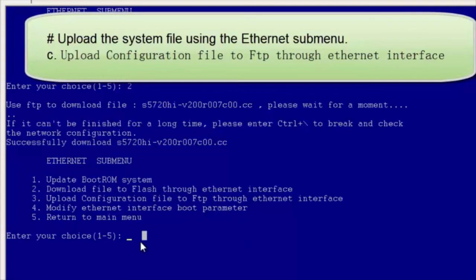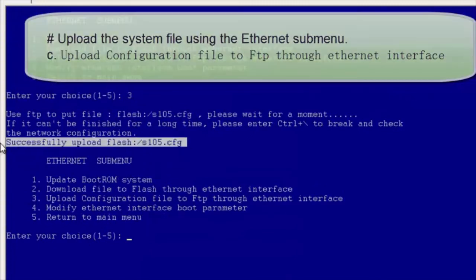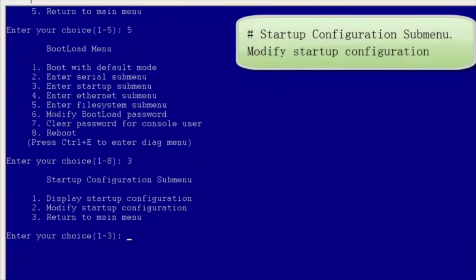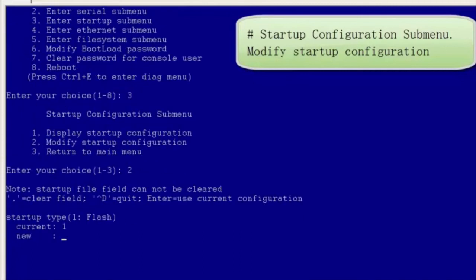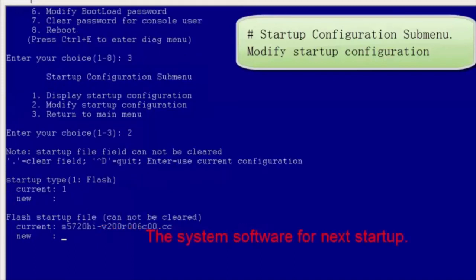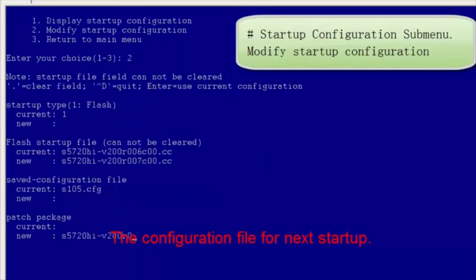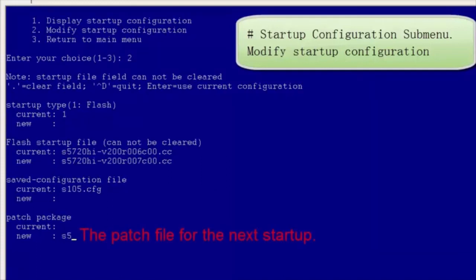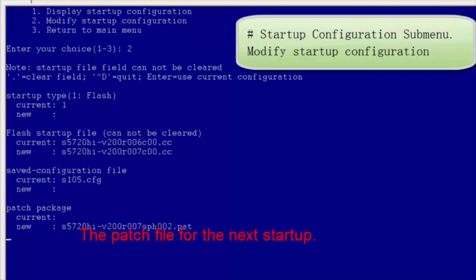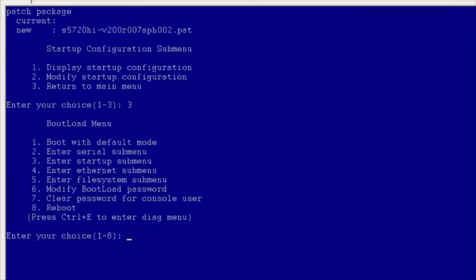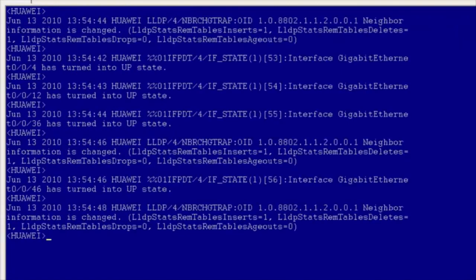Select 3 to backup the configuration file to the local PC. Return to the boot ROM main menu. Select 3 to display the startup configuration submenu. Select 2 to modify configuration information. Select the startup storage medium — in this example, we select the default storage medium. Specify the system software, configuration file, and patch file for next startup. Use the default configuration file. Return to the boot ROM main menu. Select 8 reboot to restart the switch and complete the upgrade.